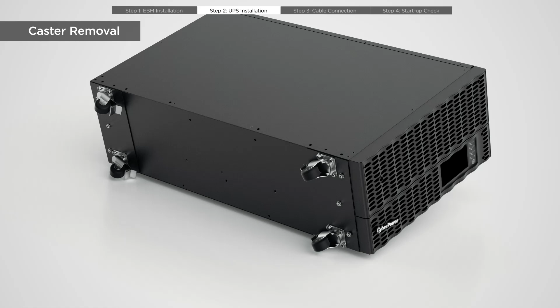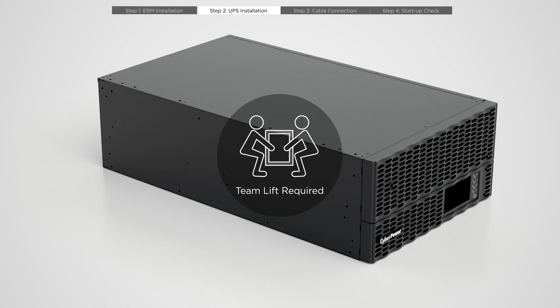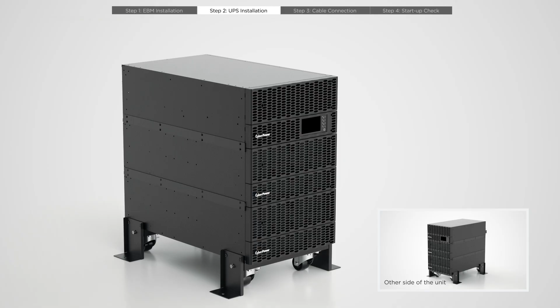Now the EBMs are installed, lay down the UPS on its right side and remove the casters. Stack the UPS on top of the EBM. Secure 2 fixed plates at the junction with 8 black flat head screws per plate.